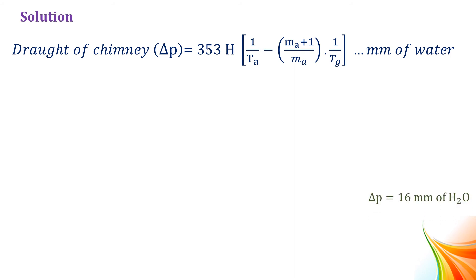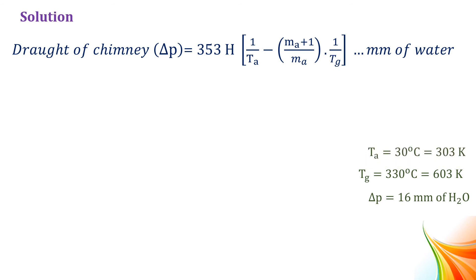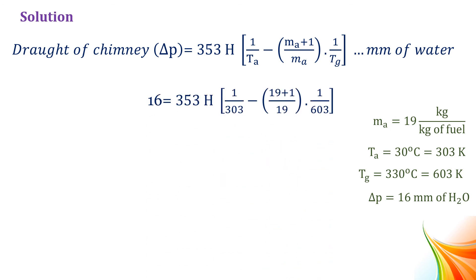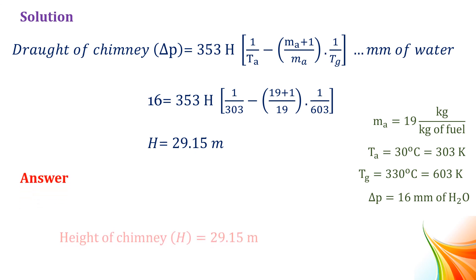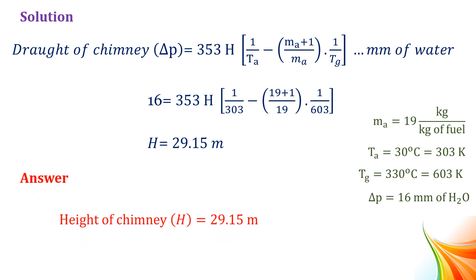In our problem, ΔP = 16 mm of water, flue gas temperature = 603 Kelvin, atmospheric temperature = 303 Kelvin, and mass of air Ma = 19 kg per kg of fuel. Substituting these values into the equation, we get H = 29.15 meters. So the height of the chimney H is equal to 29.15 meters.